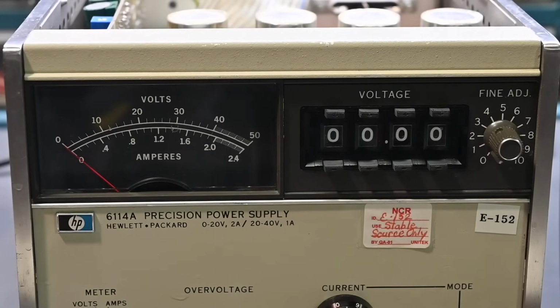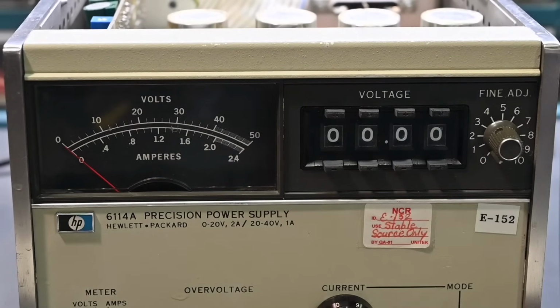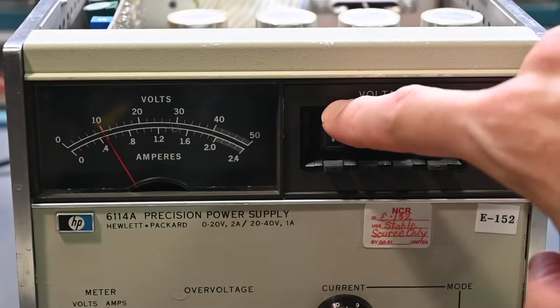So moving along with the calibration, one of the steps is to adjust the voltmeter. So on assembly number 1, it's R22, and you're supposed to adjust for full voltage output, and the meter should read within plus minus 2%. And I had noticed that this meter was reading off by just a little bit, but I made that adjustment, and now check it out. So we go to 10 volts, spot on, right on 10 volts.